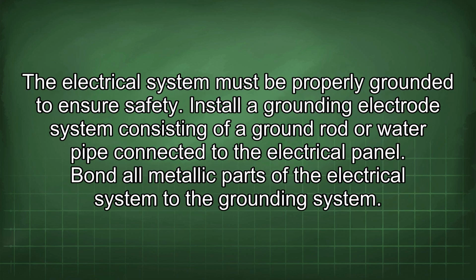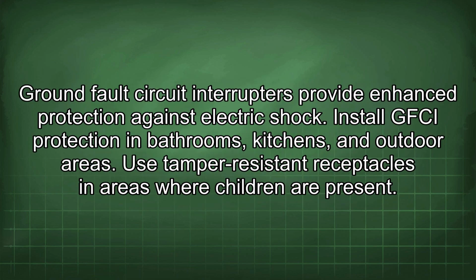The electrical system must be properly grounded to ensure safety. Install a grounding electrode system consisting of a ground rod or water pipe connected to the electrical panel. Bond all metallic parts of the electrical system to the grounding system. Ground fault circuit interrupters provide enhanced protection against electric shock. Install GFCI protection in bathrooms, kitchens, and outdoor areas.